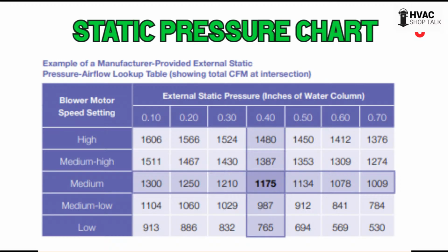So let's say you had a 2-ton system. Well, that's way too high. Actually, a better example would be a larger system, since that's probably more typical. Let's say you had a 4-ton system, typically that's 1,600 CFM. So you may have to move it up to high or medium-high. If you only had a 2-ton system and measured 0.40, you'd have to lower it down. But here's the thing with static pressure: you might measure something and say, oh, it's 1175 here on the screen, so I'll follow all the way down to low at 0.40, which is 765. That's pretty close to a 2-ton. I could do that.